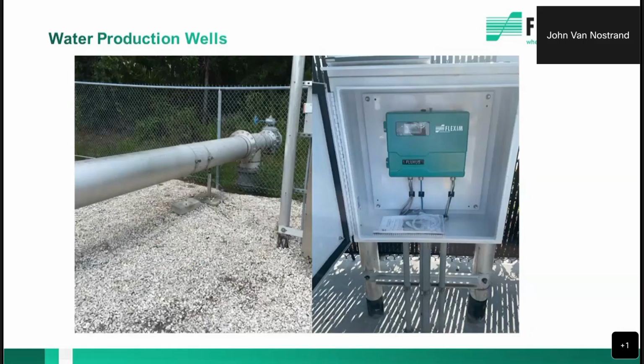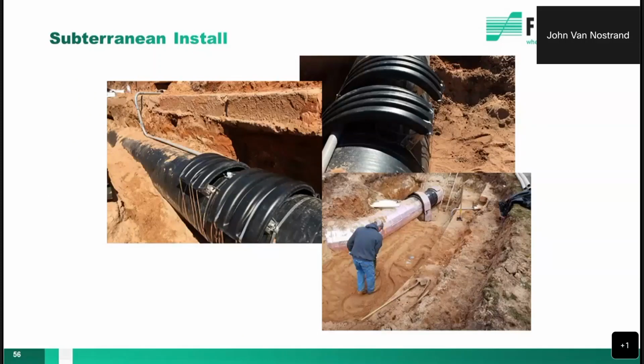It's a 12-inch pipe. They would have to take it out, reach inside, clean it with acetic acid, basically a vinegar solution, put it back in service, and it would work again. But the utility was like, I can't drive around with a crew doing maintenance on these Magmeters, so we installed the FLEXIM.